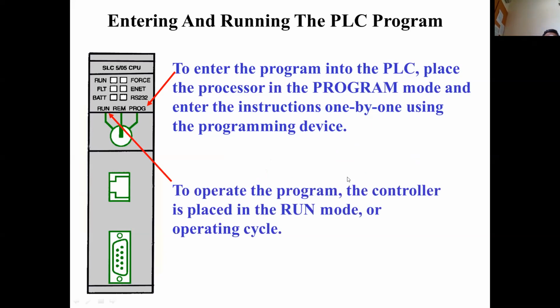Actually, in the PLC CPU, you have three modes. One is the run mode, one is the remote mode, and the program mode. While doing the PLC program, you have to switch to the program mode. Then you do the program. Once the program is over, you can switch it into the run mode, so the controller will run the program.